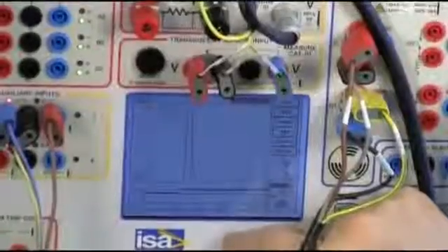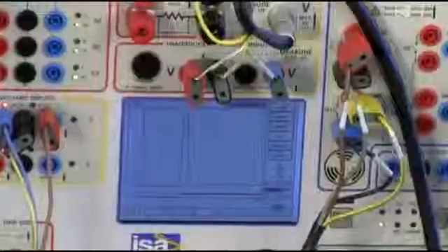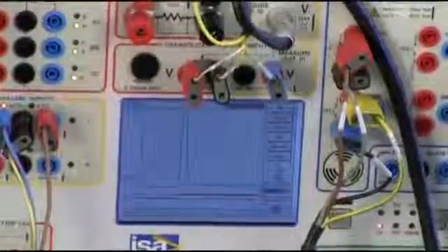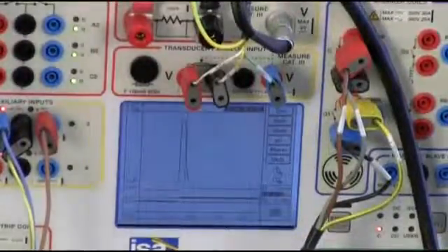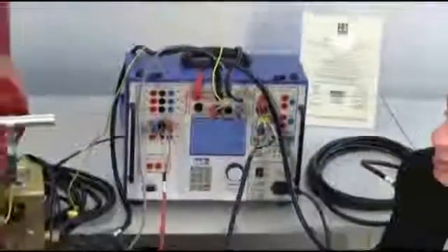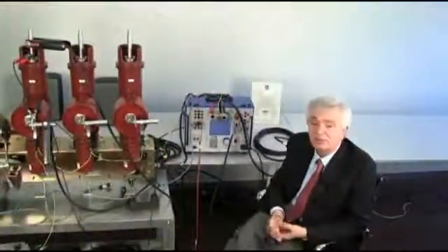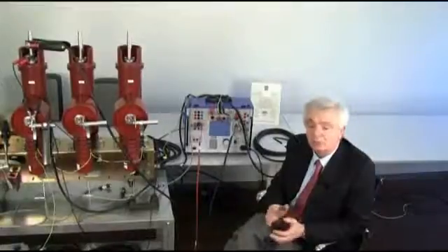And then that's okay. So, in conclusion, here again, if during the close I had some trembling because of plays caused by loose nuts or whatever it was, I would see it immediately. In conclusion, I can repeat my dynamic testing on all three phases, and thanks to this I am assured that there is nothing wrong on the movement mechanism.